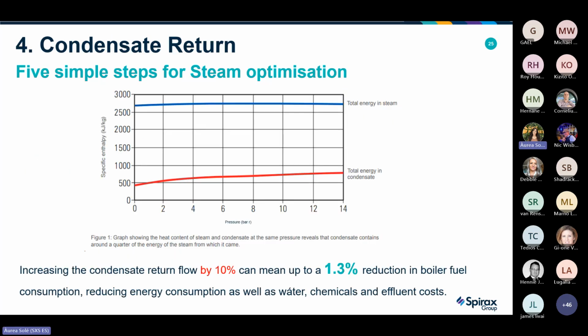If we move to the fourth top optimized solution that we always suggest our customers look at, and we help them calculate the energy savings, it is returning the condensate. Condensate is valuable energy, and condensate recovery saves money as well as energy, because it contains about 25% of the energy from the original steam. So returning this condensate with its sensible heat to the boiler feed tank reduces fuel use directly. We have the rule of thumb that by increasing the condensate return flow by 10%, this can mean up to an average 1.3% reduction in the boiler fuel consumption.